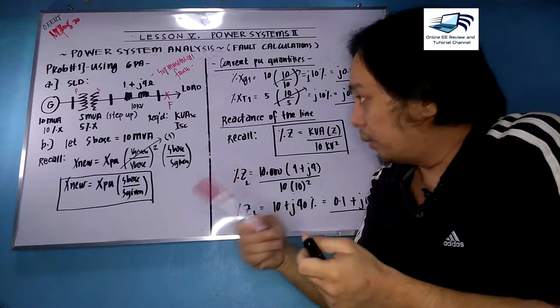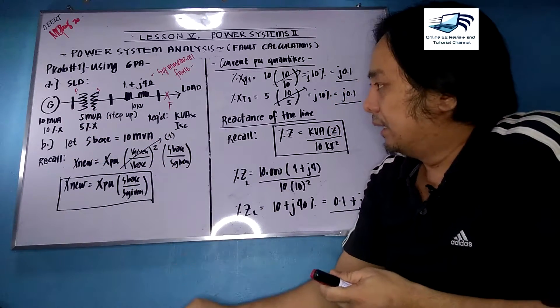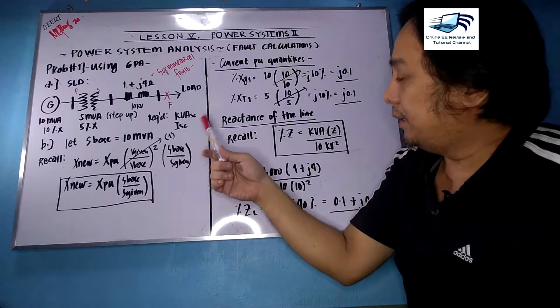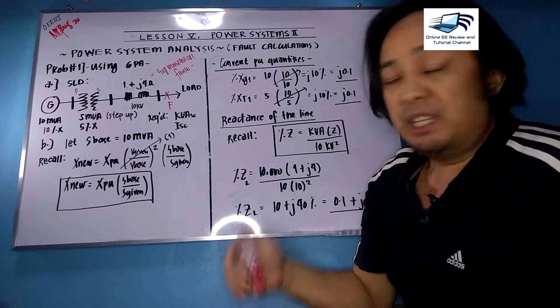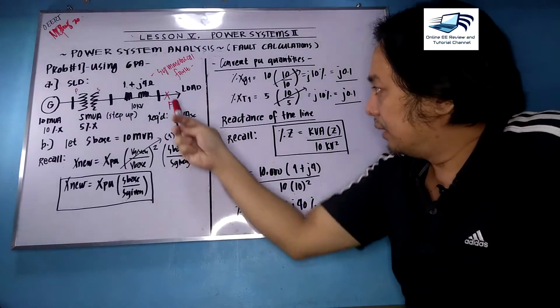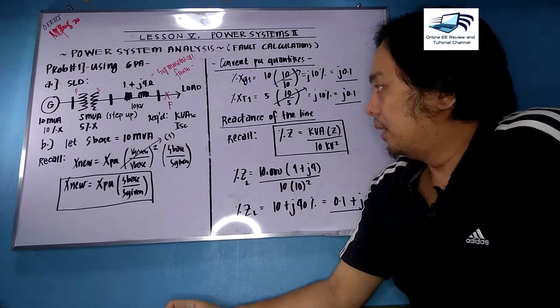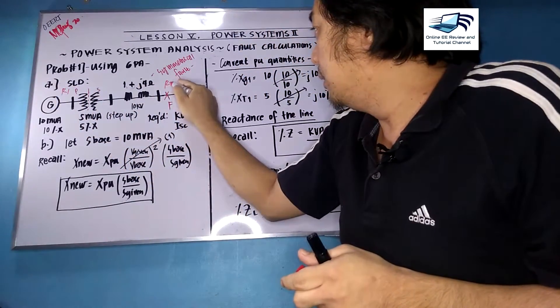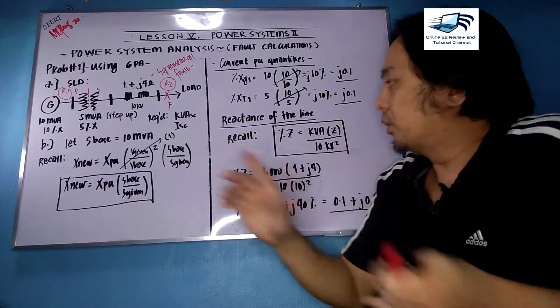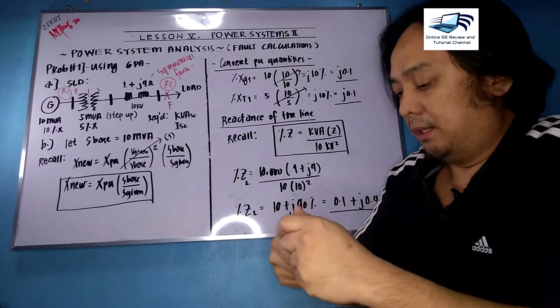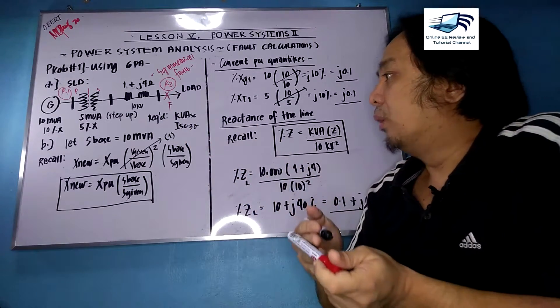We need the percentage reactances and the apparent powers, which we will convert in the next steps. The required quantities from the problem — since the fault occurs at the load end, you have two regions: Region 1 and Region 2. The required outputs are short circuit KVA (KVA_SC) and ISC for the three-phase fault.